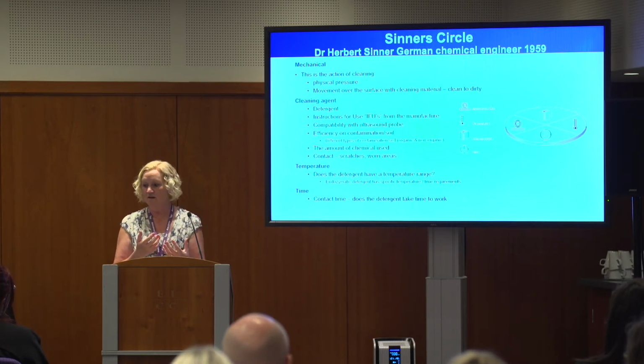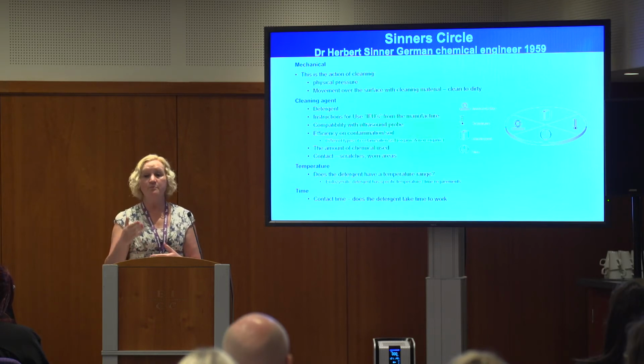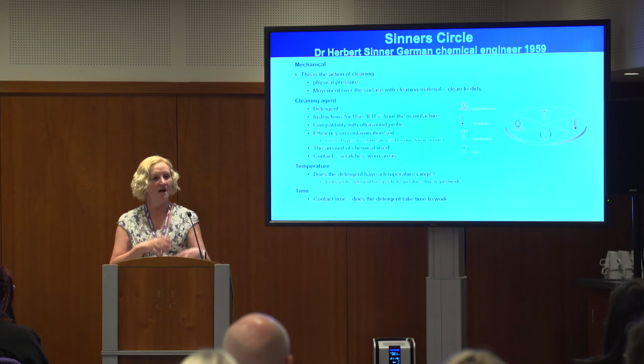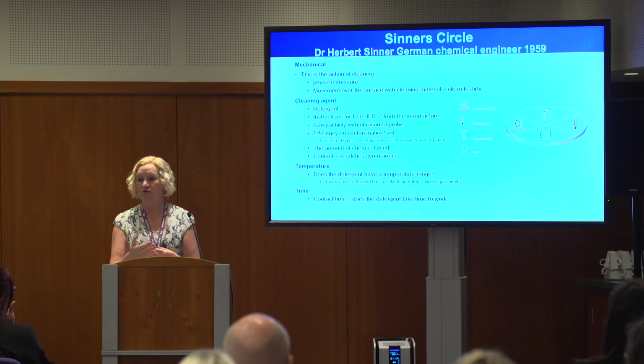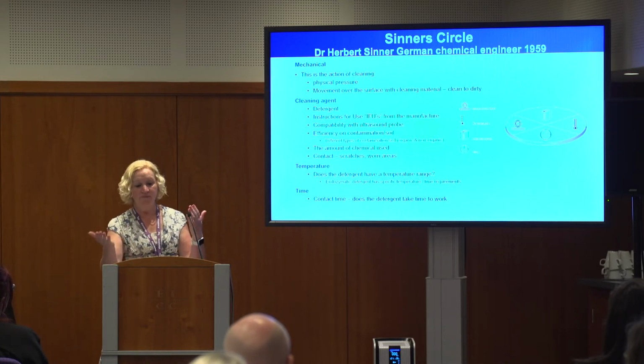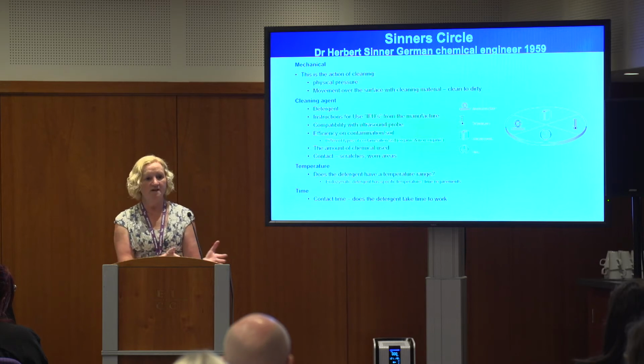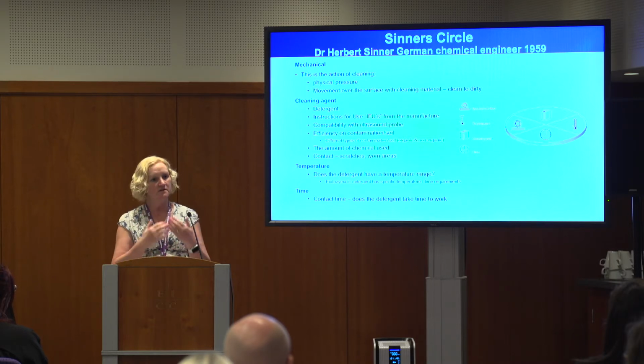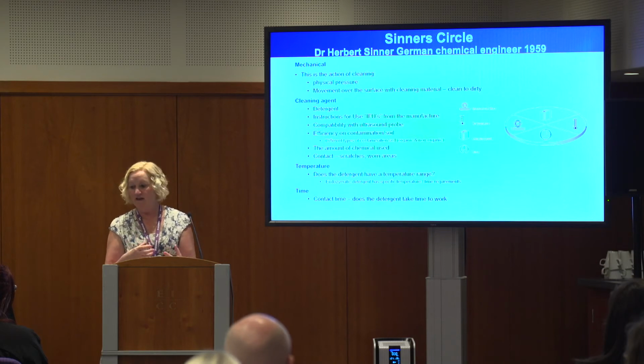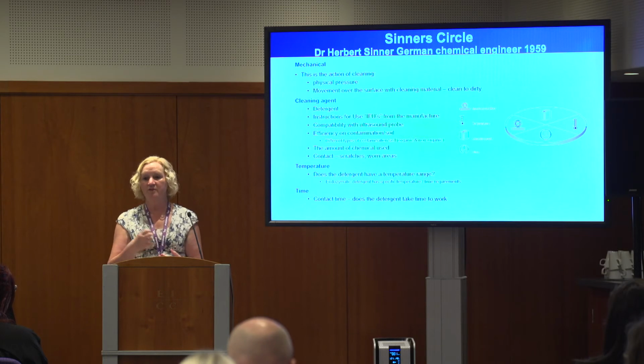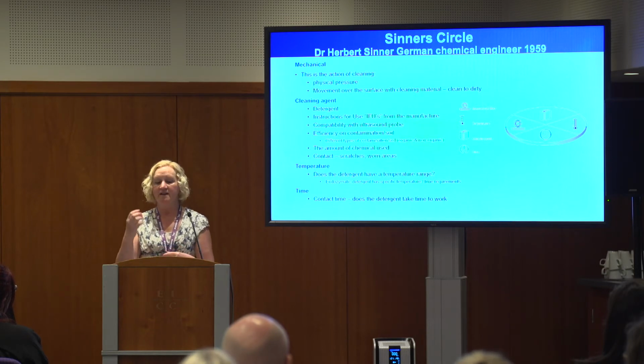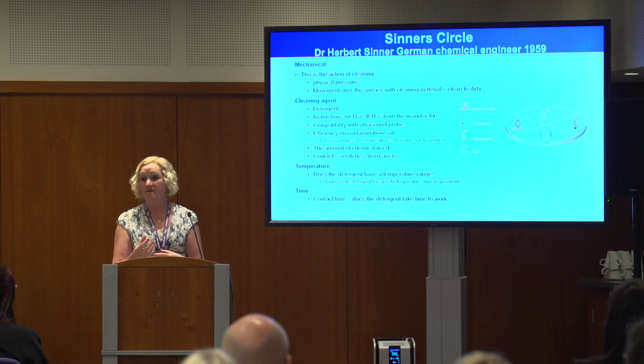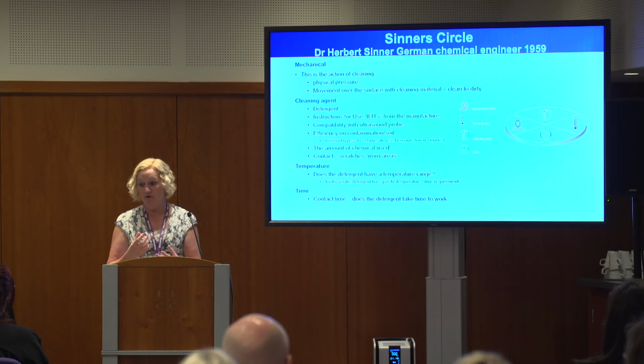Look at the detergent you're using. What do the IFUs from the manufacturer of the probe say you can use? What do the IFUs from the manufacturer of the detergent say you can use it on? You might have two different detergent wipes. One has a minute contact time, one has a 30-second contact time. Unless you read it, you don't actually know. So you need to look at that. Compatibility, effectiveness. What is on that probe that you need to clean off? You've got gel, you've got bodily fluids, possibly. What are you trying to clean off? The gel will be a different type of contamination to bodily fluids. Is the detergent wipe that you're using effective at getting both off?